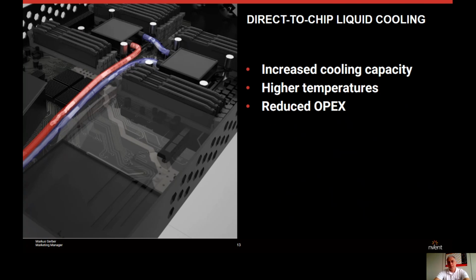Why should I do this? The advantage is you can increase your cooling capacity by having this solution, because the servers are getting more and more powerful. You will not have only one CPU, you will have several CPUs inside, and you can really increase the capacity. And the temperature inside the equipment is much higher, so the liquid inlet temperature needed to cool a server is higher than in a traditional room layout. And this allows you, of course, also to reduce your operational costs.